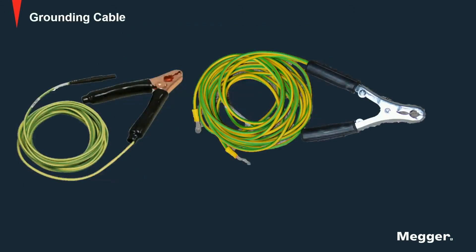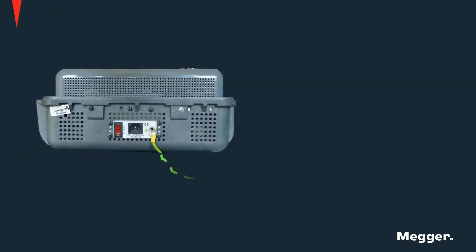Using the grounding cable provided with this unit, find a good grounding point and make a solid ground connection. Proper grounding is essential to obtaining good results. Remember that the ground terminal should be the first one to be connected and the last one to be disconnected. A solid ground connection is very important when it comes to testing current transformers.